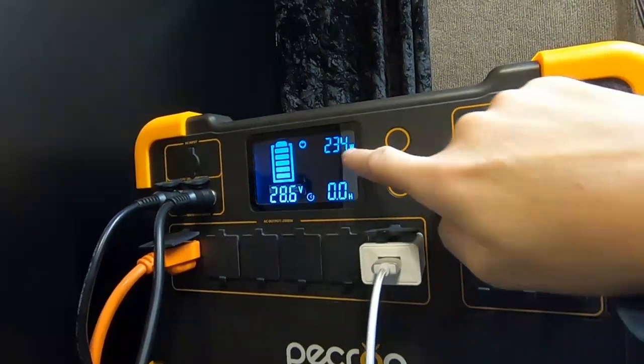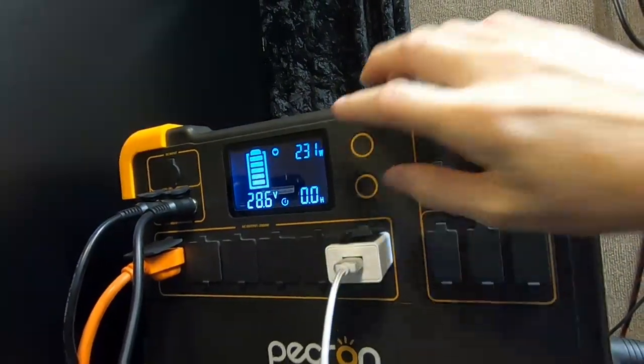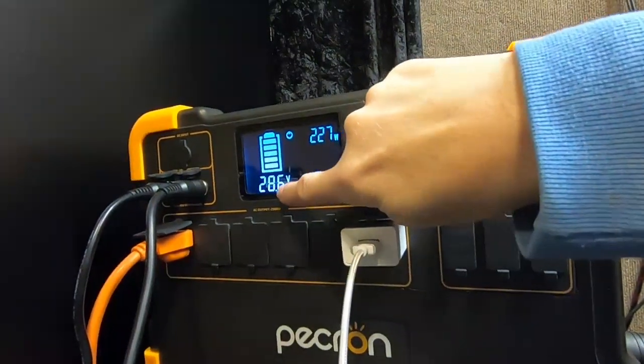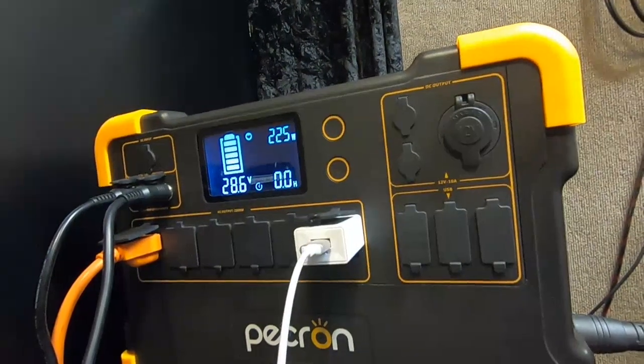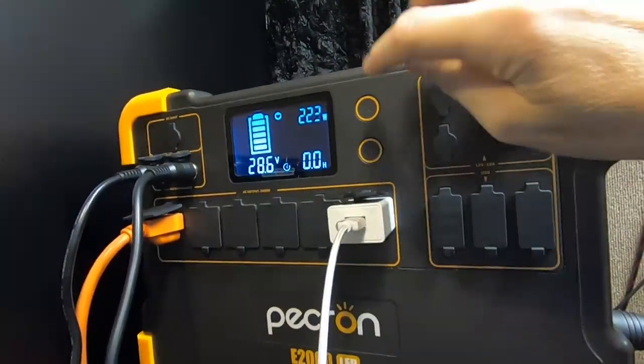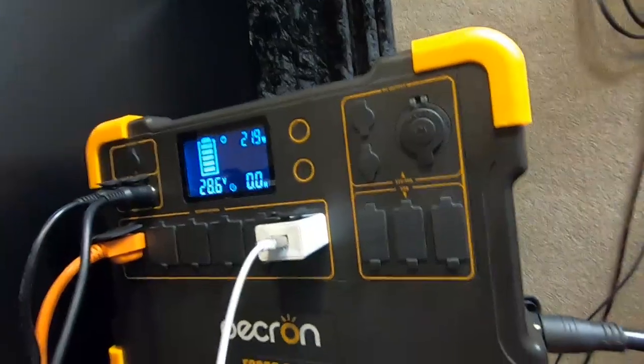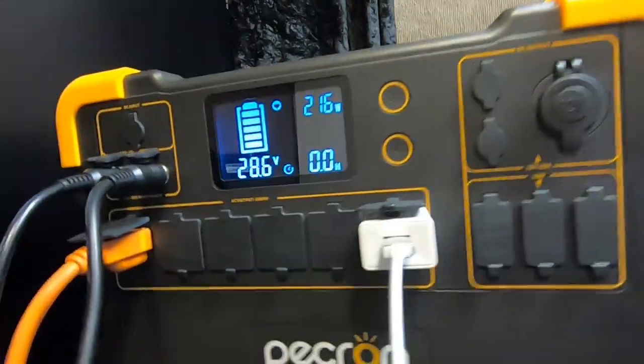You can see how it's whittling down — every second or so it's dropping another watt, trying to find those last little bits of space to put the energy. It probably won't reach 28.7 volts until this is all the way down. I've noticed that 28.6 is a good charge, but 28.7 seems to be where this system says that's enough energy.